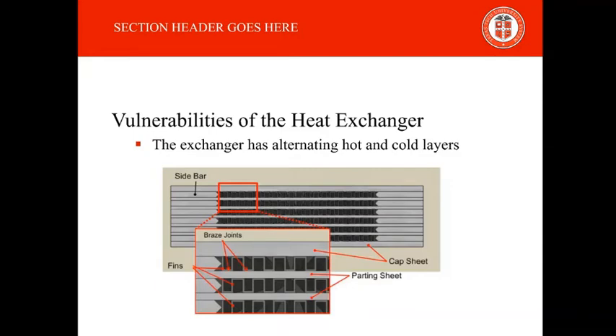The fins' connection to the cap and parting sheets is critical to the structural integrity of the brazed aluminum heat exchanger. When the layers are pressurized, the fins act as a truss and counteract the fluid forces on the cap and parting sheets. The benefits of choosing a brazed aluminum heat exchanger are highly efficient heat transfer and a compact design that can accommodate many different process streams.